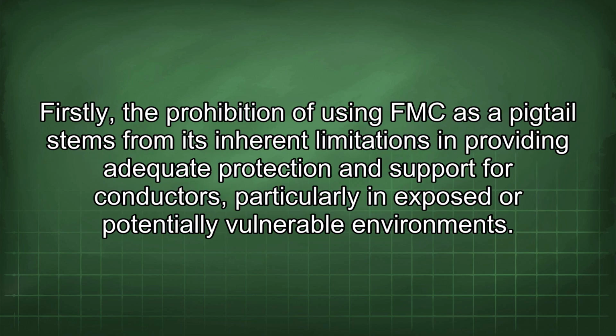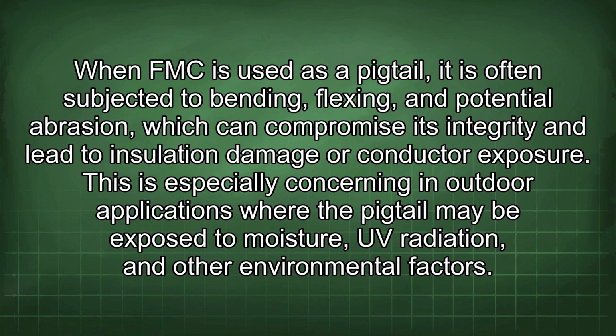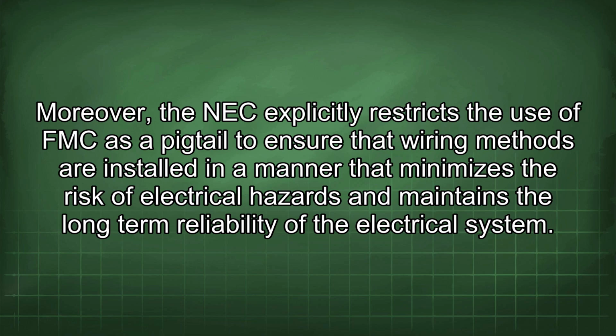Firstly, the prohibition of using FMC as a pigtail stems from its inherent limitations in providing adequate protection and support for conductors, particularly in exposed or potentially vulnerable environments. When FMC is used as a pigtail, it is often subjected to bending, flexing, and potential abrasion, which can compromise its integrity and lead to insulation damage or conductor exposure. This is especially concerning in outdoor applications where the pigtail may be exposed to moisture, UV radiation, and other environmental factors. Moreover, the NEC explicitly restricts the use of FMC as a pigtail to ensure that wiring methods are installed in a manner that minimizes the risk of electrical hazards and maintains the long-term reliability of the electrical system.